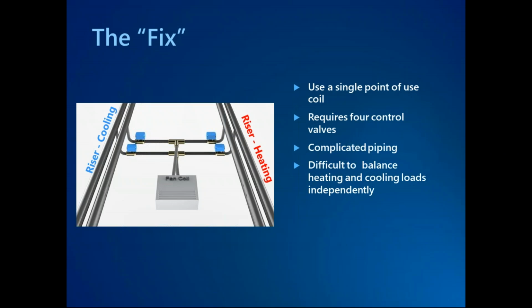So the fix that people came up with was to take this four-pipe system and tie it into a two-pipe coil. And this was done by using 4 two-way control valves, 2 on the heating side, 2 on the cooling side. When the heating side was open, the cooling side would be closed, and you'd have hot water circulating through your fan coil. Vice versa, you could have your heating closed, your cold water open, and you would be getting cold water going to either your fan coil or your chilled beam zone.